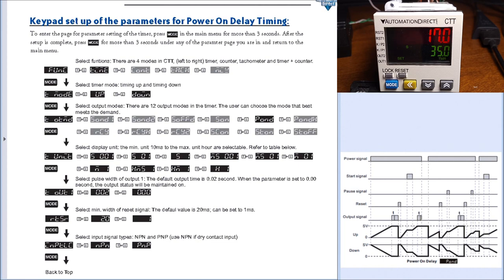Now I will turn power off to the unit. As soon as I turn power back on again you can see it automatically resets and it will start timing up again until it reaches the set value of 35 seconds and turn on my outputs.